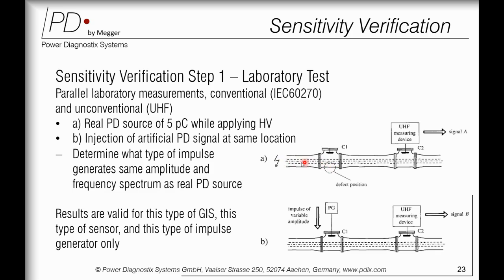When they energize the GIS, the known 5 pC defect will be captured. Once it is confirmed as a 5 pC defect, you de-energize the GIS. At the same time, when it is energized, you also capture from the UHF device in your GIS. Let's say you have applied 220 kV, and for the known 5 pC defect, what you capture is 30 dB microvolt.